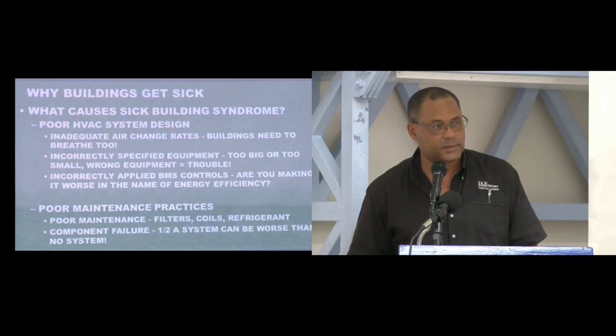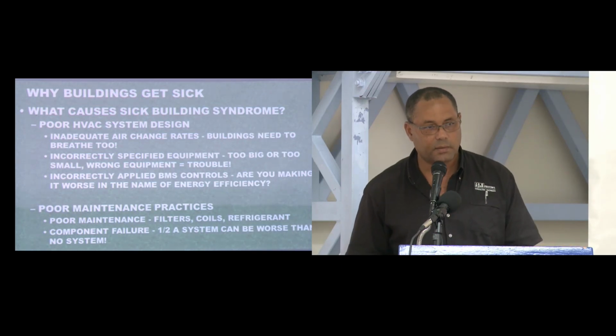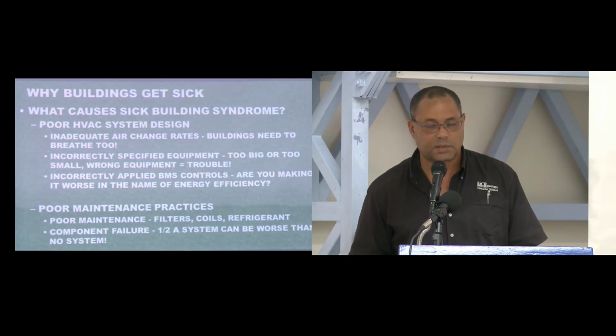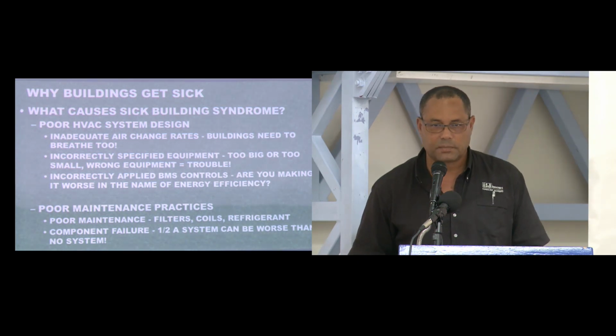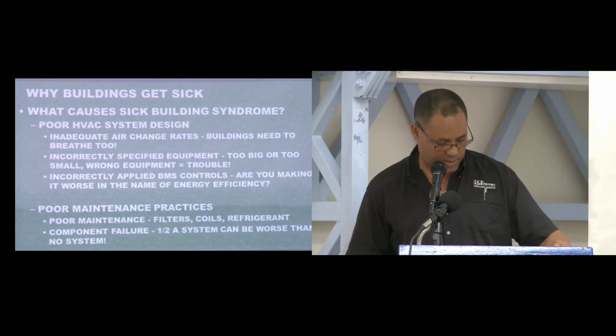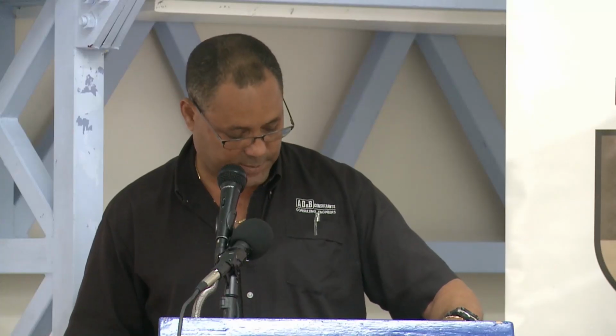This last one might surprise you: component failure. A half a system can be worse than a whole system, or no system at all. The reason for that is that you still have cold air, but you're not dehumidifying. You can work in this scenario. People can still come to work, still function, but your humidity levels are high, your indoor air quality drops, and people start falling asleep, they start getting sick. It's worth it just to keep your maintenance on a consistent basis.